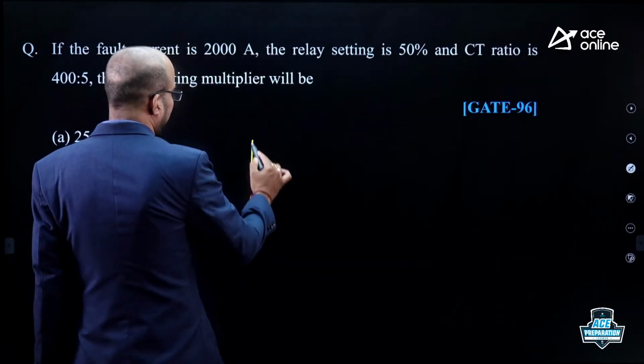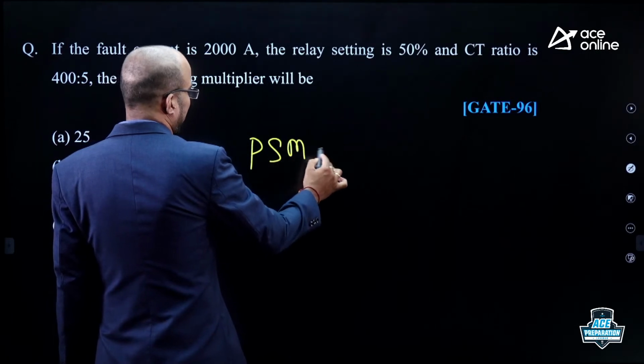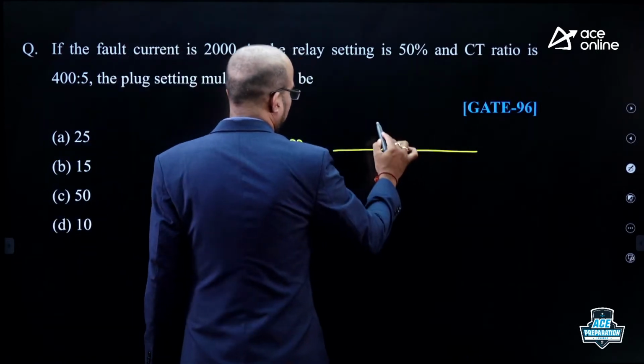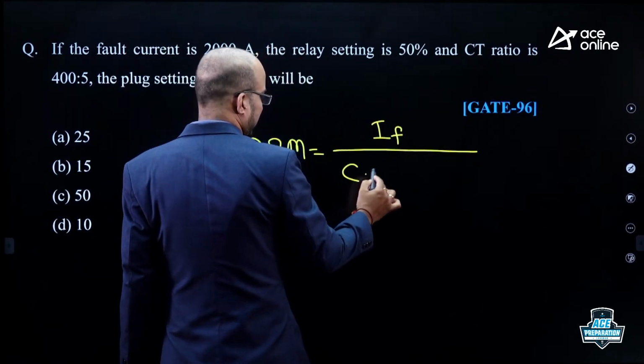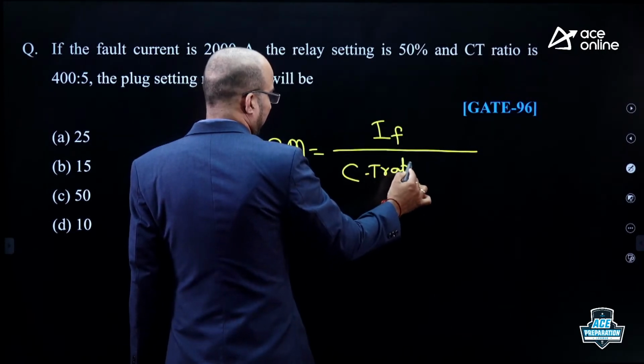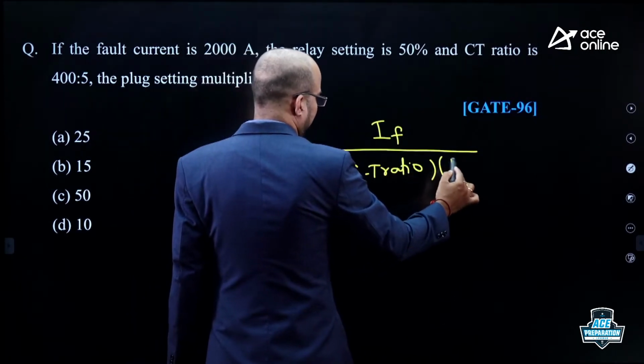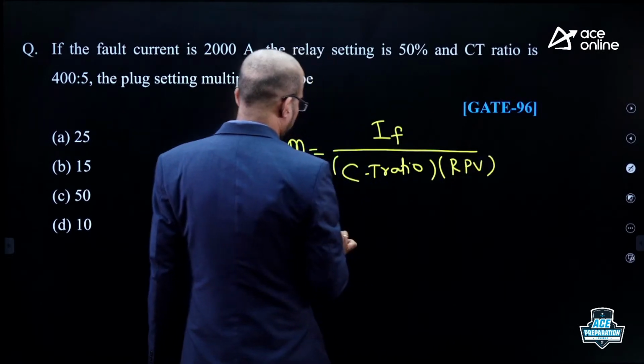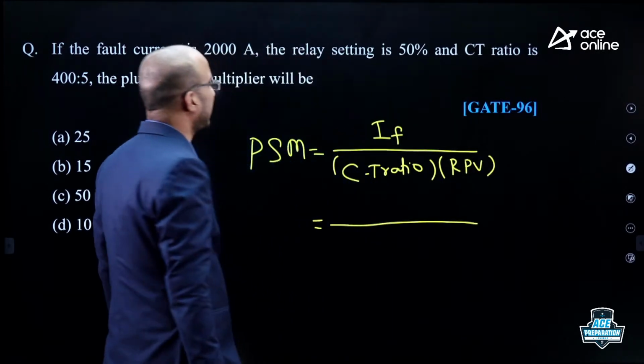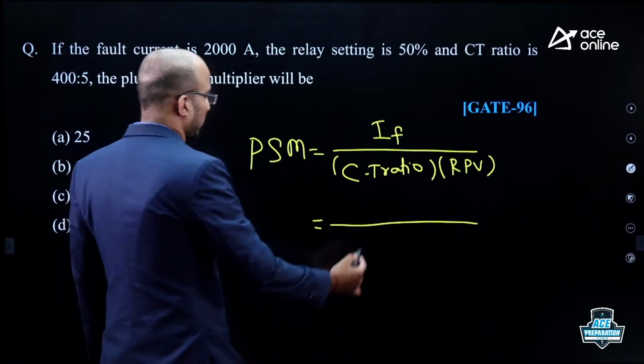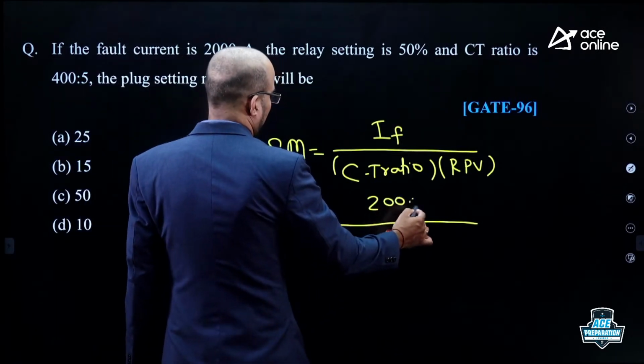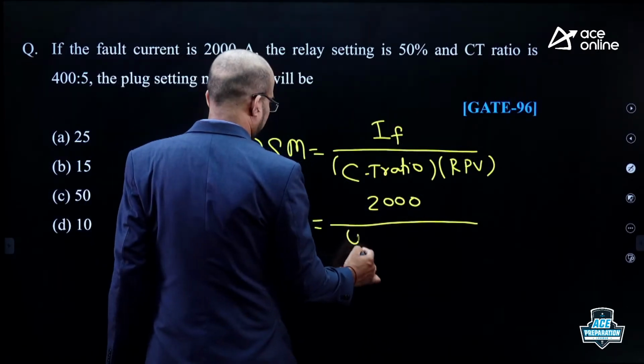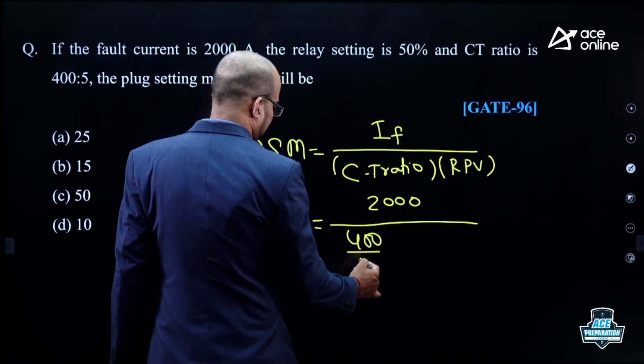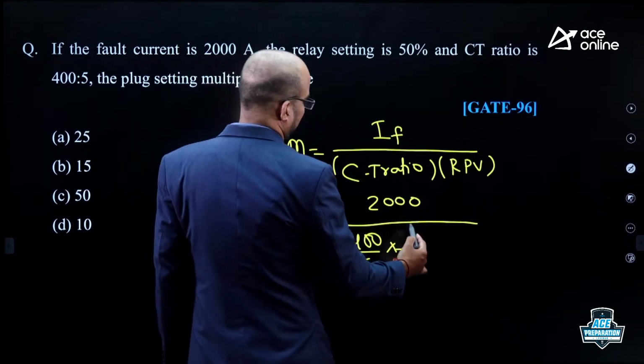So here he is asking to calculate the plug setting multiplier. PSM is equal to what? Fault current by CT ratio multiplied with relay pickup value. So here, if you observe the question, he has given the fault current as 2000 amperes, CT ratio 400 by 5, multiplied with relay pickup value.